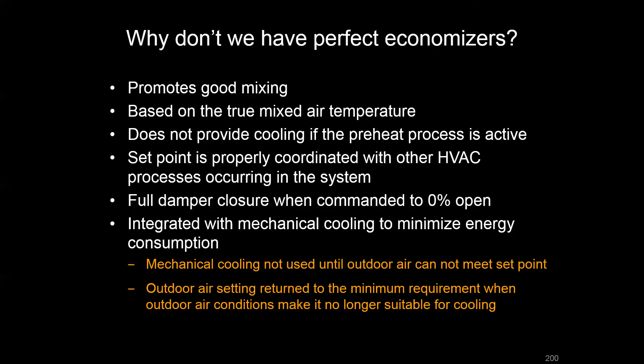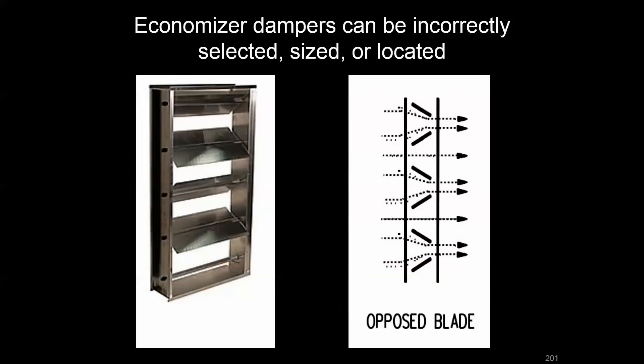So why don't we have perfect economizers? There are many things that need to go right, and only a few that can go wrong to cause performance problems. Poor mixing results from improperly sized dampers, bad relative positioning, or selecting the wrong damper type — such as an opposed-blade type that won't redirect airstreams into one another — leading to inadequate mixing in the mixed air plenum.